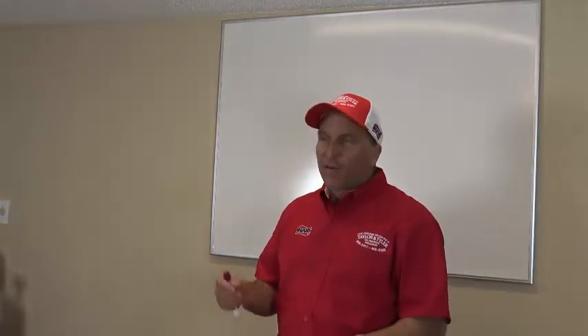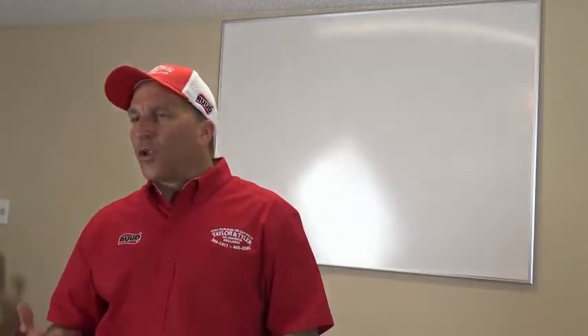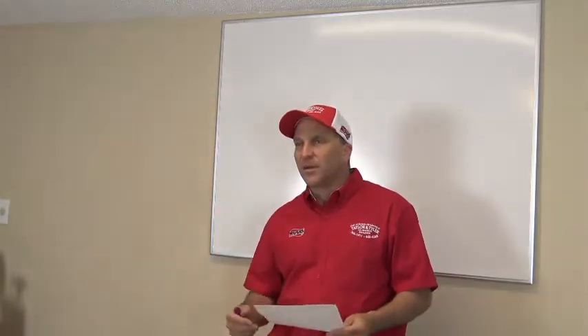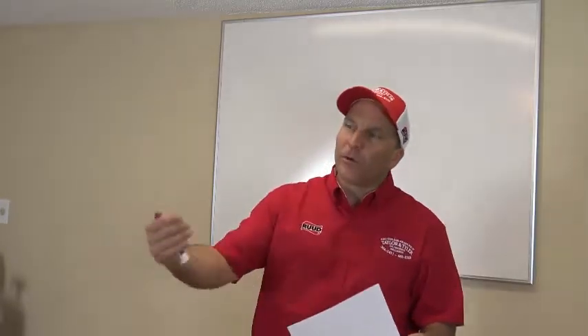Compressor amps. You're going to have your run load amps and your lock rotor amps. So what we just did with a hard start kit, guys, I recorded your run load amp 16, and I recorded your lock rotor amps at 116, right? I bring that into you and I say, look, sir, your compressor run load amps is 16, your lock rotor amps is 116. I'm going to recommend putting a hard start kit on your system to lower that amperage down. I'm recording everything for you. This is what we do when we go to a job. I'm going to tell you the performance of your system and what I can do to improve the performance of your system. That's my job when I go to your house.